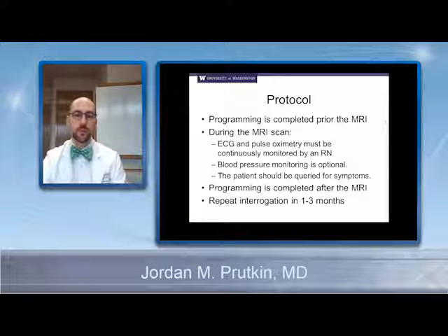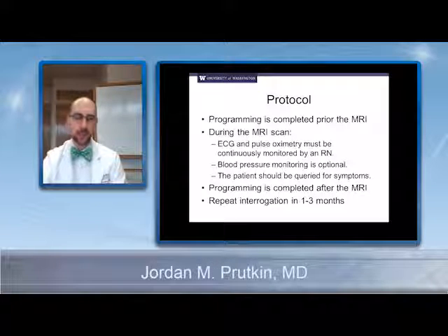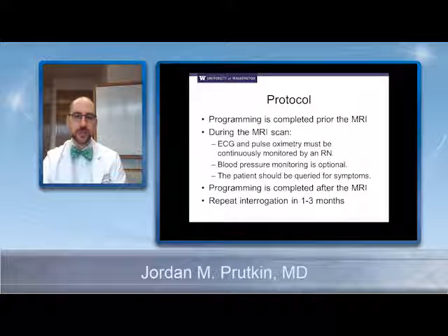Our protocol, the way we do it, is that we review the records beforehand to be sure that the patient doesn't have any abandoned leads, epicardial leads, etc., and that the generator has been placed within or since the year 2000. And then we will consent the patient, and then we will program the device, interrogate it, and program it just prior to the MRI.